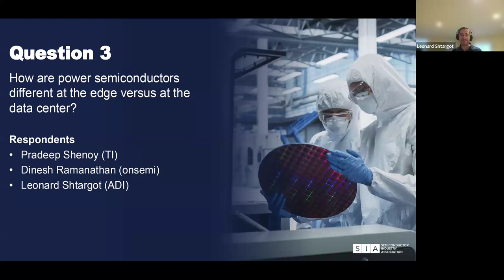Yeah, absolutely. I want to call back to a couple of my other panelists to set up the problem here, because the semiconductors are going to evolve to meet the challenge, and really it's a two-factor thing. The one Leonard introduced is the challenge of getting energy from the grid to a central point. You've got high voltage generation that needs to go through multiple steps down to a GPU, which is now consuming 1 kilowatt plus of power. Along that way today, you're losing 10 to 15% of that energy as heat, and that's not acceptable as we're trying to scale these things up. We need to save every joule of energy that we can, and semiconductors are the ones shaping that energy, very critical to evolving that.